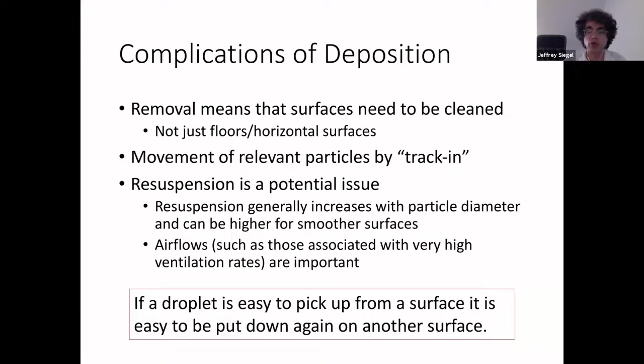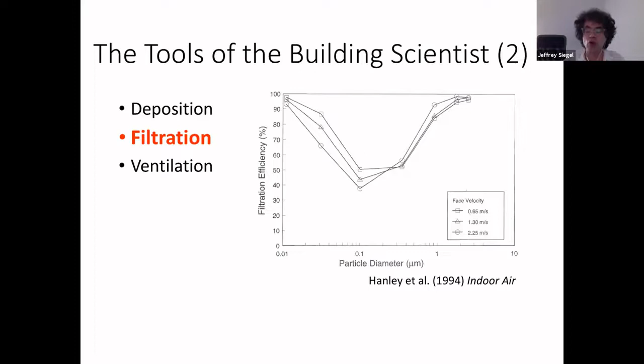There's also been discussion of filtration as a means of removing particles. I show this somewhat complicated plot for one simple reason: filters don't have a constant efficiency for all particle sizes. They typically show a U-shaped curve, and every filter has a different one—generally more efficient for very small and very large particles, with a dip in between. So discussing a filter requires more nuance than a single efficiency value, which is usually addressed with a reporting or rating system. One example is an ASHRAE standard, which is where MERV ratings come from.